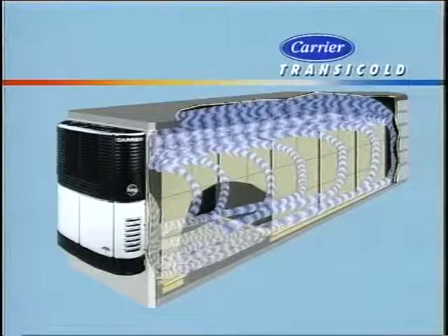If any portion of the keypad does not light up, there is a problem that needs to be brought to the attention of the shop supervisor. The unit will shut down for a few moments, and the microprocessor will then begin test number 2. At this point, the pre-trip will become automatic, and you can leave. Pre-trip generally lasts for 7 to 14 minutes, and at the end will show either pre-trip pass or pre-trip fail if a problem was detected.